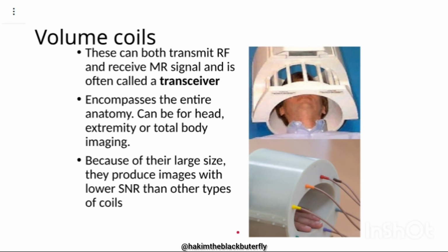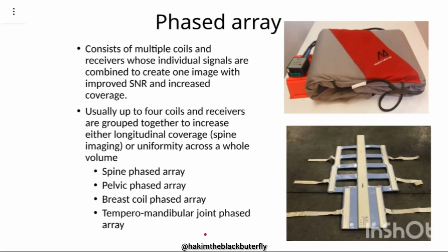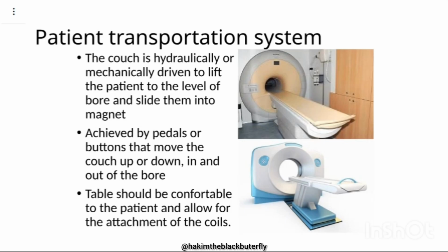Usually up to 4 coils and receivers are grouped together to increase either longitudinal coverage, that is the spine imaging, or the uniformity across a whole volume. So you find different phased coils for different body parts. For example, for the spine, we have the pelvic phased array coil, the breast coil, then the temporomandibular joint phased array. The phased arrays are normally receiver coils and also the surface coils. It's in most cases the volume coils that are transceivers, but these other ones are receiver coils. So what is going to be acting as the transmitter is the total body coil that is inbuilt within the MRI system.